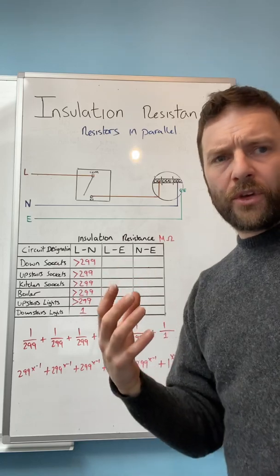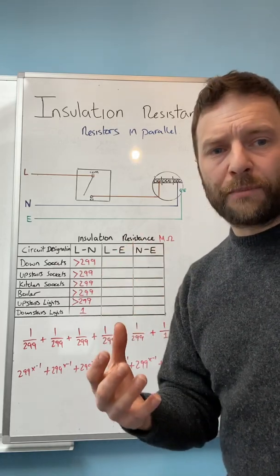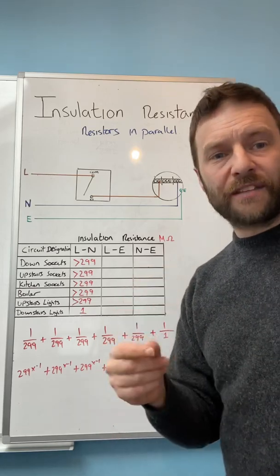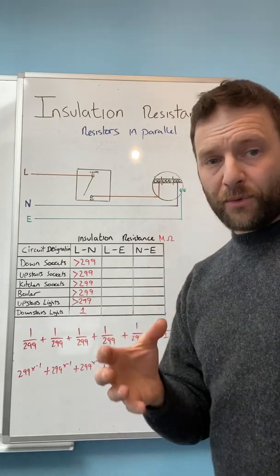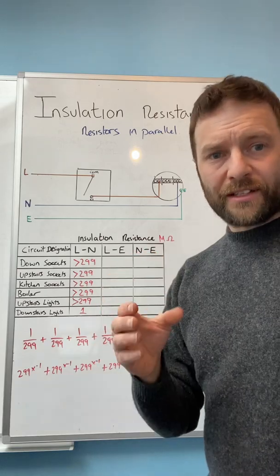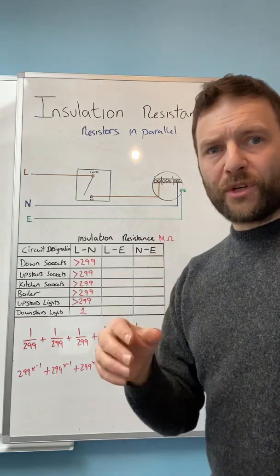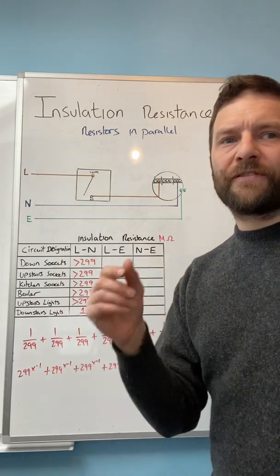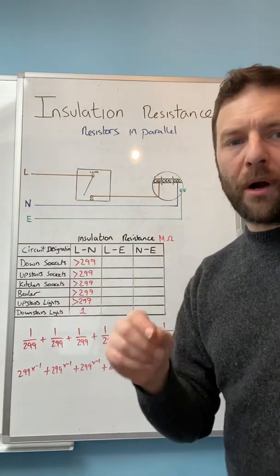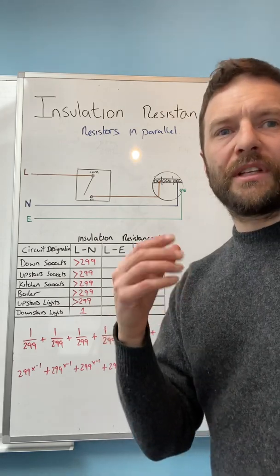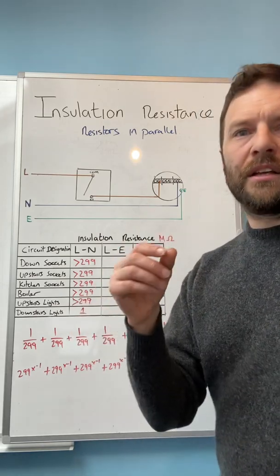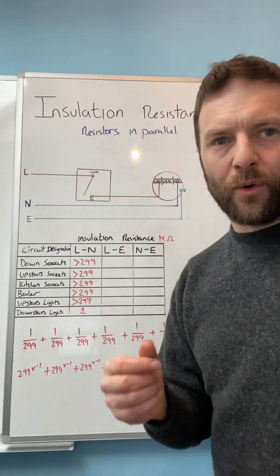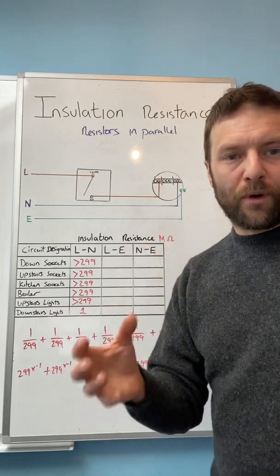So for instance if you look at regulation 643.3.2 it says the insulation resistance measured with the test voltages indicated in table 64 shall be considered satisfactory if the main switchboard and each distribution circuit tested separately with all of its final circuits connected but with current using accessories and equipment disconnected has an insulation resistance not less than the appropriate value in table 64. And obviously that value is one mega ohm.